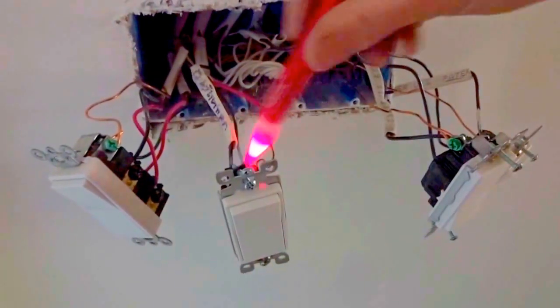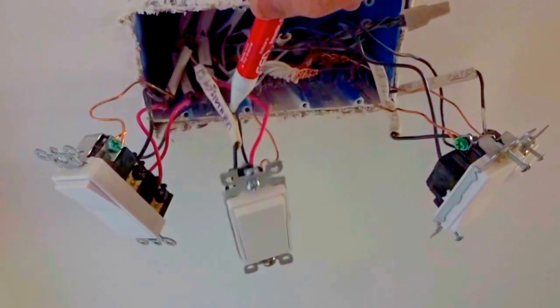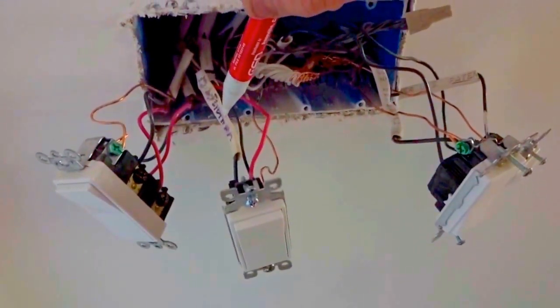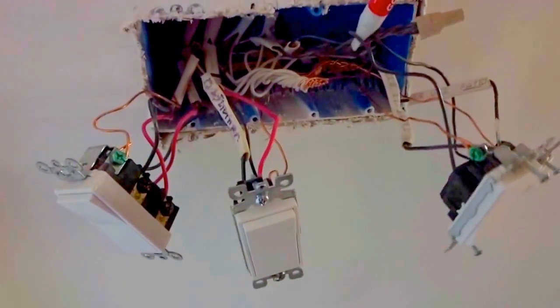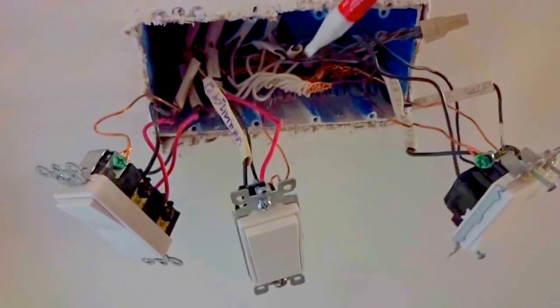This three-way switch with the switch leg and the travelers will also have the neutral isolated from the other two circuits, and then on down to this one. So instead of all the neutrals being under one wire nut, there's going to be three separate wire nuts for the neutrals.